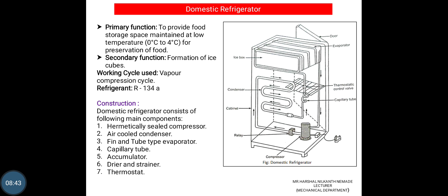Construction: a domestic refrigerator consists of the following main components: hermetically sealed compressor, air cooled condenser, fins and tube evaporator, capillary tube, accumulator, dryer and strainer, and thermostat. A domestic refrigerator has a cabinet shape. In its basement the compressor is placed, and at the back side the condenser and receiver are arranged. The evaporator remains exposed inside the refrigerator cabinet storage. Ice trays are kept in the evaporator for producing a small quantity of ice.